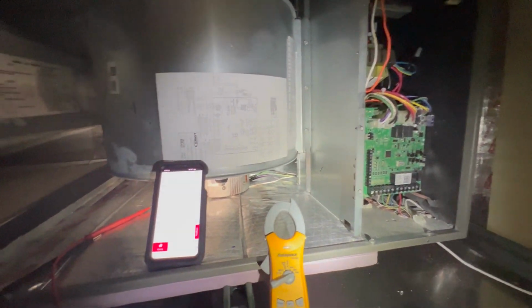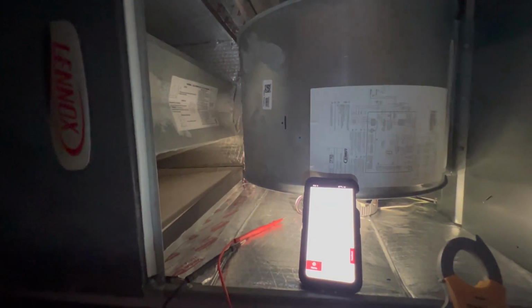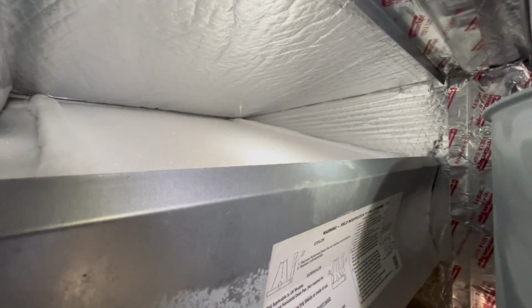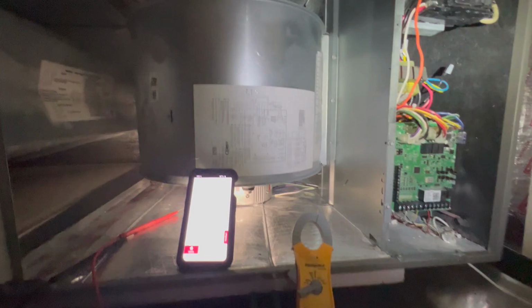So we out here checking this unit. You guys can see the evaporator coil. It's got some frost in it. It's got ice all the way to the outside around the compressor. So this is for the master bedroom.